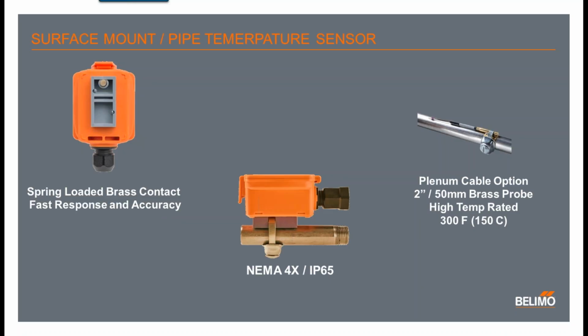Our surface mount and pipe temperature sensors are available with NEMA 4X enclosure or a plenum cable option. The NEMA 4X housing version has a spring-loaded brass contact sensor which ensures a very fast response and high accuracy. The plenum cable type has a 2-inch brass probe for fast response, and the cable is also plenum rated and high temp up to 300 degrees Fahrenheit.